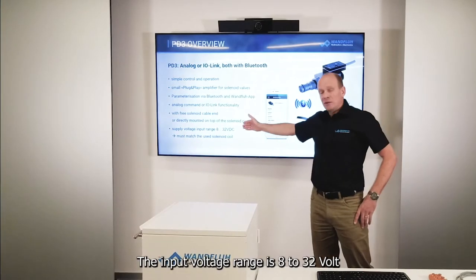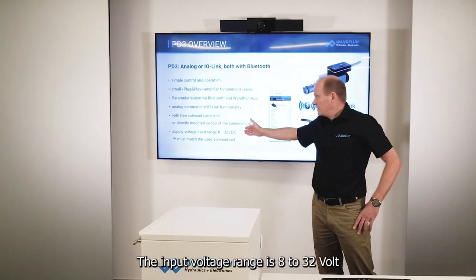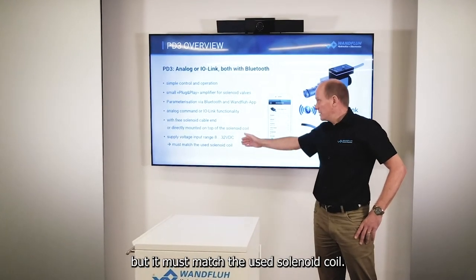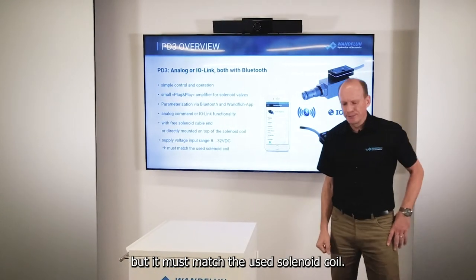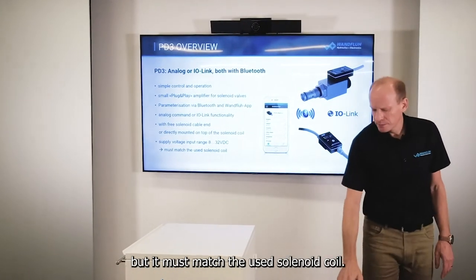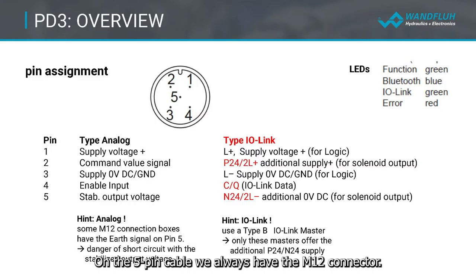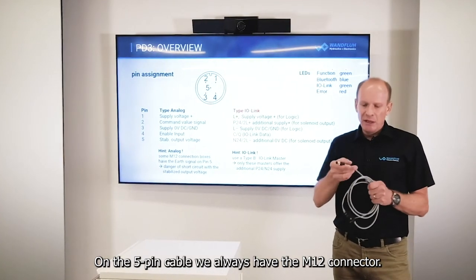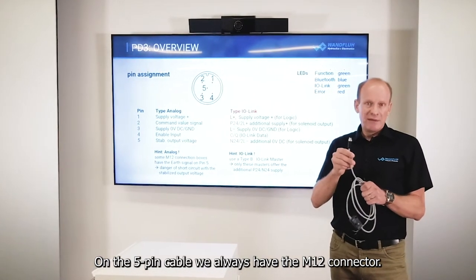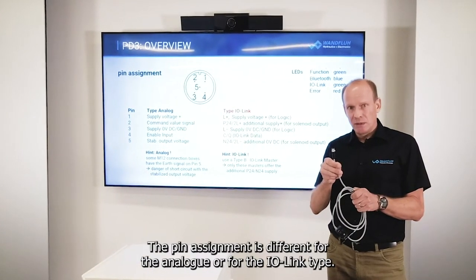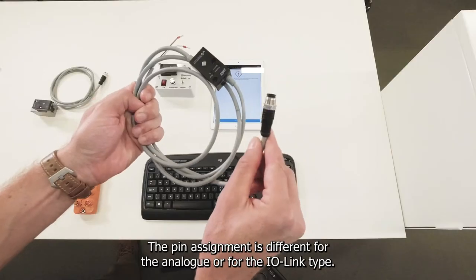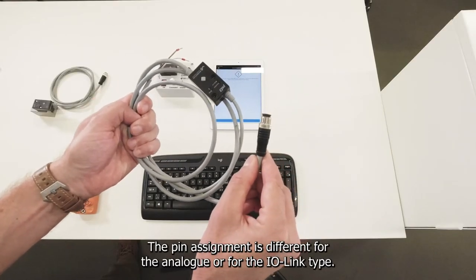The input voltage range is 8 to 32 volts, but it must match the used solenoid coil. On the 5-pin cable of the PD3 we always have the M12 connector. The pin assignment is different for the analog or for the IO-Link type.